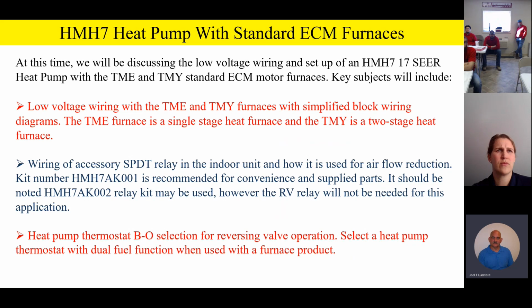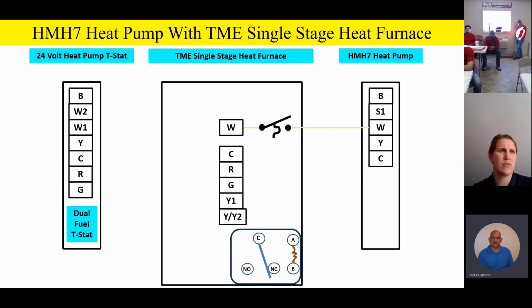And please remember that if you're going to do a dual fuel, don't forget that your heat pump has to have that BO selection, but it also has to have dual fuel capability. And most of your modern heat pump thermostats can do dual fuel, but just remember, if you're going to do dual fuel, you have to have a thermostat that's compatible for a dual fuel application. And so this is going to look very, very similar to what we did before. Like I said, I'll kind of breeze through all this, but you're going to use that little construction thermostat we just talked about if you're going to do dual fuel.